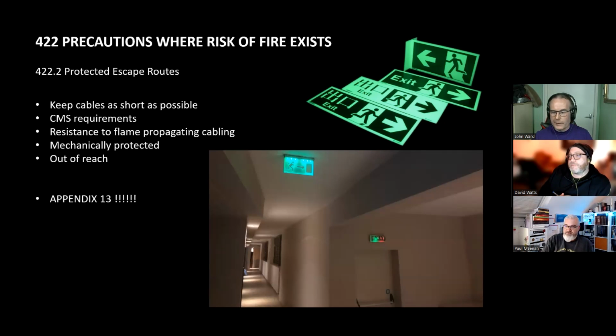There's lots and lots of stuff in this 422, and to be honest with you, we could do a whole webinar on it, but I'm not going to. Some of the guidance effectively says keep cables as short as possible. CMS, don't use plastic, which to me, as we said in our DPC, John, is the death of plastic trunking. Resistance to flame propagating cabling, why not? Why wouldn't you? Mechanically protected, kept out of reach, and read Appendix 13. And that's really all I'm going to cover. It's very much the same kind of thinking we always have for locations with stored combustible materials, where we'd say only go in if you have to, don't have any joints, have the systems be non-flame propagating, don't do any unnecessary stuff in there. It's just expanding on that now for these protected escape routes.